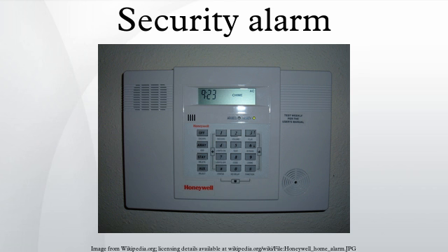Independent certification. Some insurance companies and local agencies require that alarm systems be installed to code or be certified by an independent third party. The alarm system is required to have a maintenance check carried out every 6–12 months to ensure all internal components, sensors and PSUs are functioning correctly. In the past, this would require an alarm service engineer to attend site and carry the checks out. With the use of the Internet or radio path and a compatible IP radio transmitting device, some checks can now be carried out remotely from the central station.